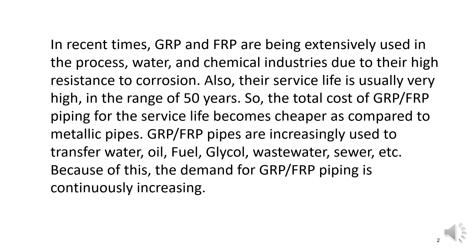Also, their service life is usually very high, in the range of around 50 years. For carbon steel pipes, which we normally design for 20-year duration, GRP or other plastic pipes can work successfully for more than 50 years. So the total cost of GRP and FRP piping over the service life becomes cheaper compared to metallic pipes.